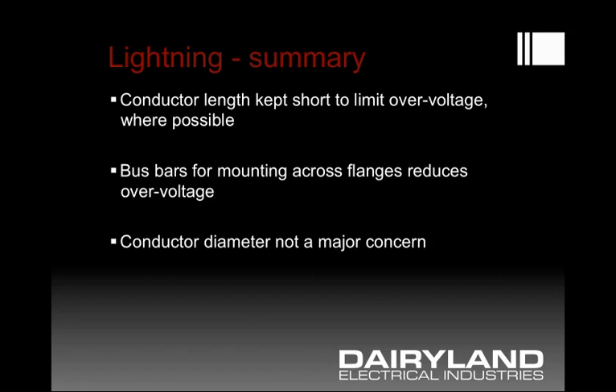Bus bars provide the best overvoltage limitation because they have lower inductance and produce lower voltage than a flexible conductor system. If you do use conductors, you want to limit the length, and diameter isn't that big a factor. You just want to have an appropriate ampacity for your system — that's where diameter comes in. But increased diameter doesn't greatly help the inductance problem; rather, that comes from length limitation.